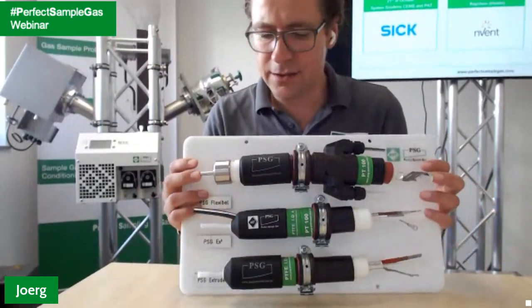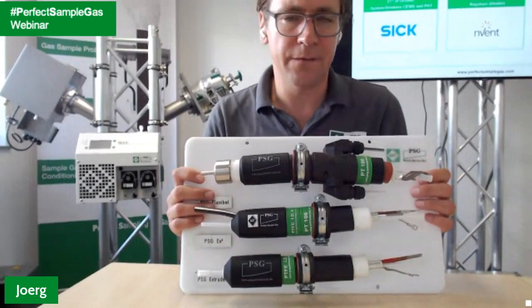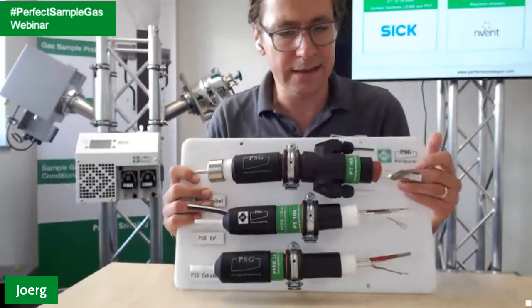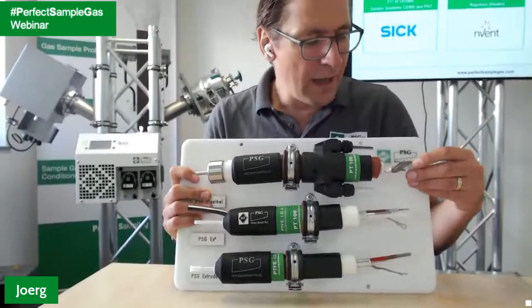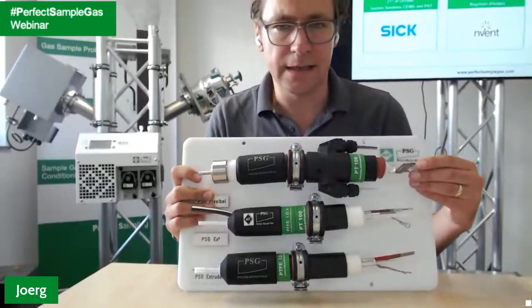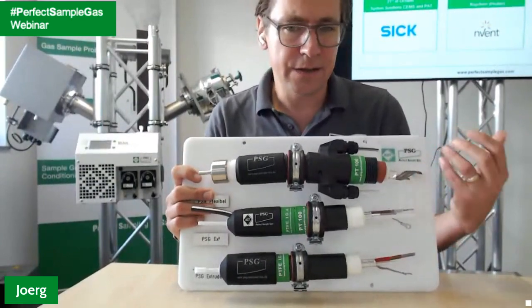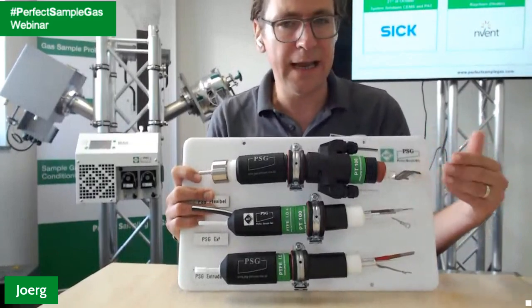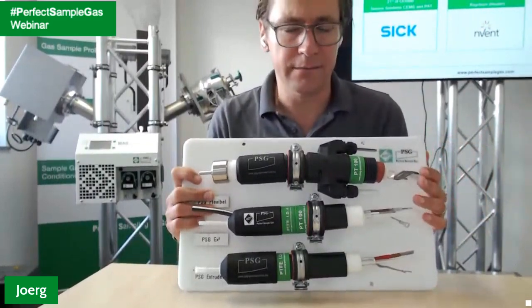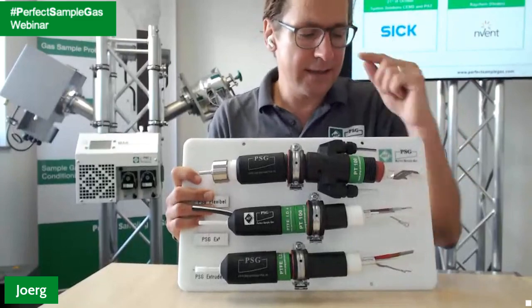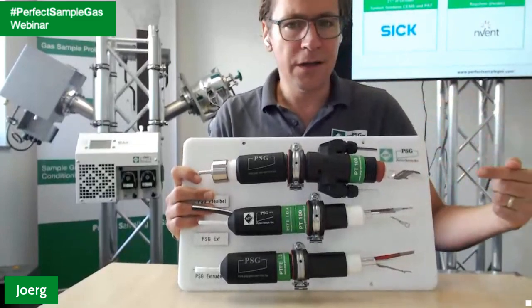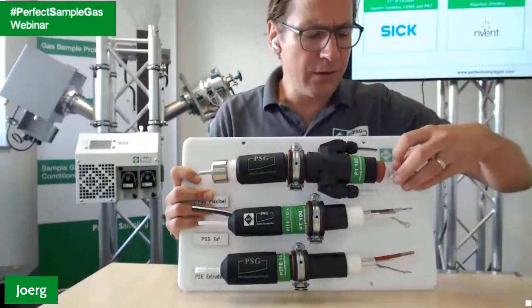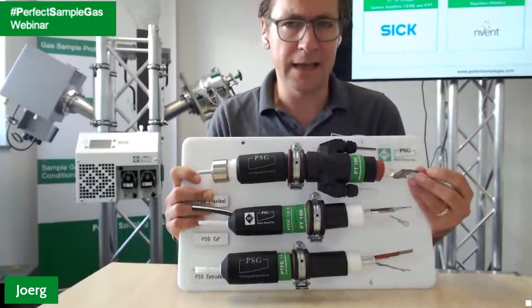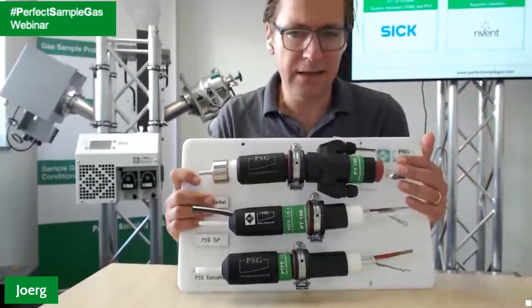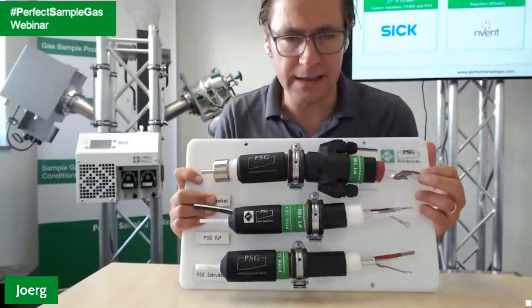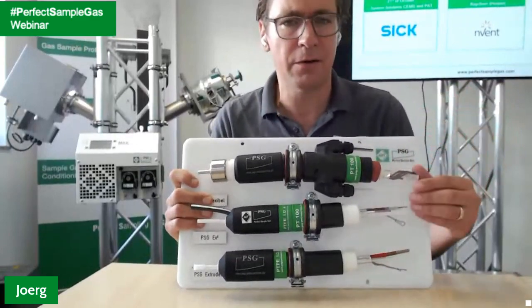In this technology, the flexible heated sample lines, it's often combined with a so-called fixed resistance heater. That means there's a certain power output designed on the length of the line. The advantage is it is wrapped around, so there's a lot of power you can bring into this type of line. 90 watts, even 120 watts per meter is possible. So there's a lot of power.